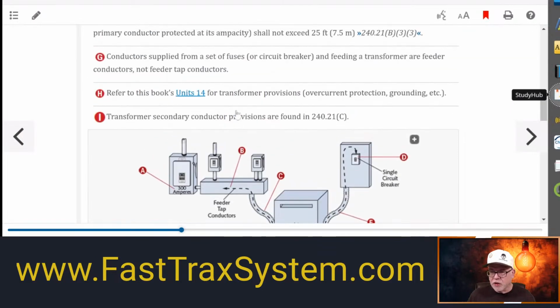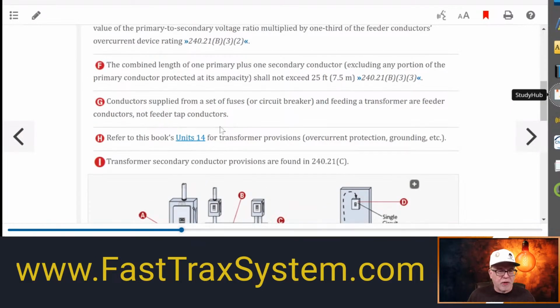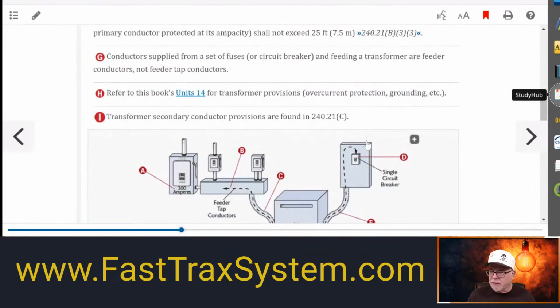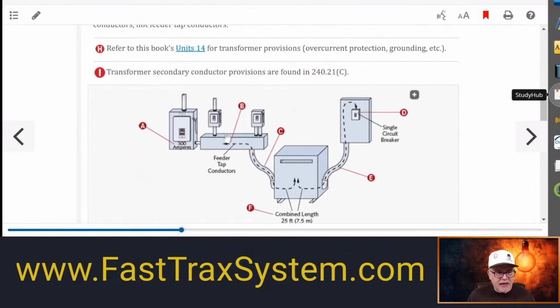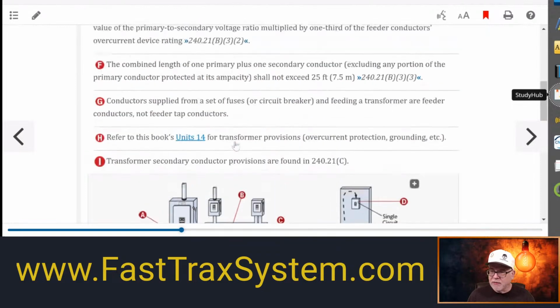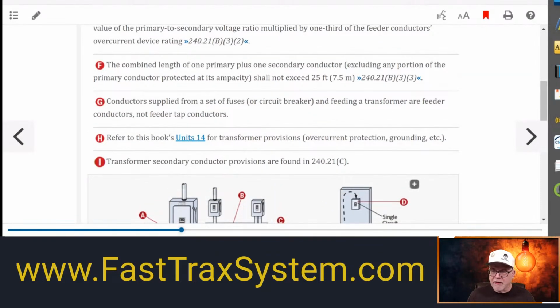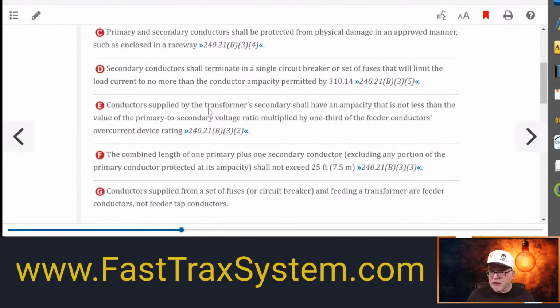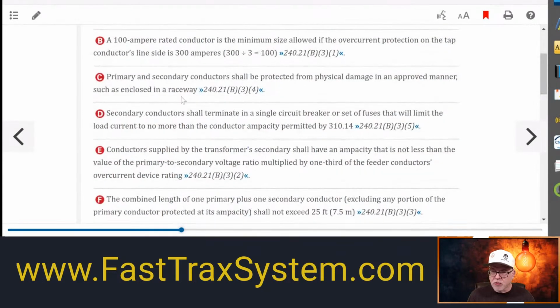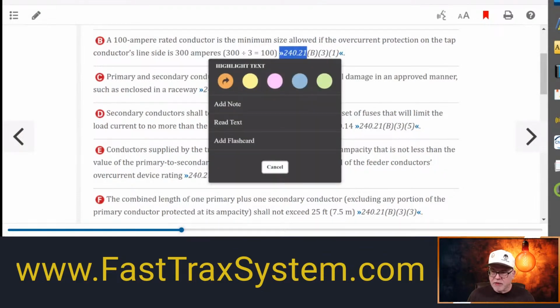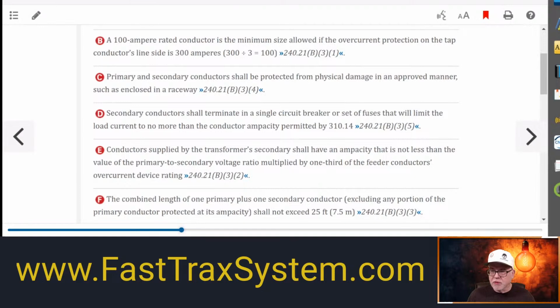Now, you have to remember there are rules, and again, in our reference in our book, we do give you references back to 14. That's just where we were for all the transformer provisions. But right now, we're talking about what happens for this being able to tap a feeder. How does this change the conductor size? Okay, all right. Well, this is what we're looking at right here, is all these rules in 240.21 B3, okay, B3. So let's go look at that in the code real quick.